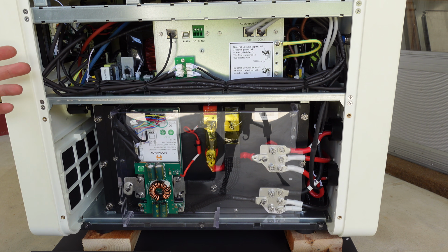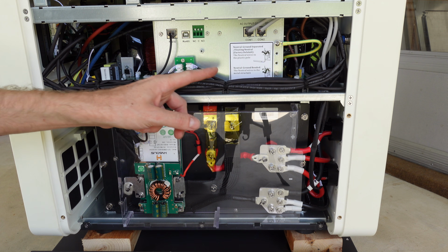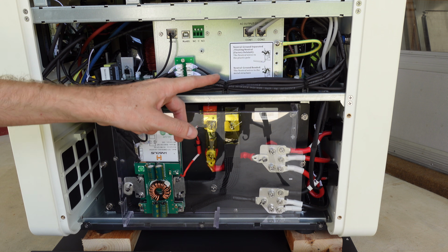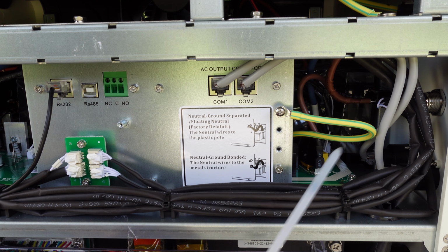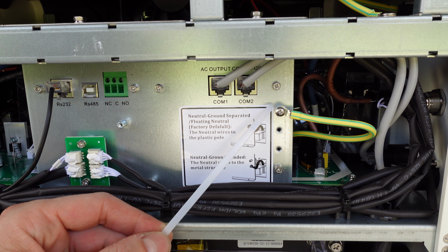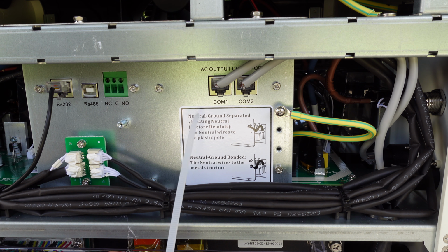The first thing worth mentioning is that cover is designed to be user removable by you, the customer. The reason for that is over here on the top right, we have our ground neutral bond. By default, these units ship with this conductor attached to a plastic bushing. It says here the neutral ground bond is separated, so you have a floating neutral in this configuration.